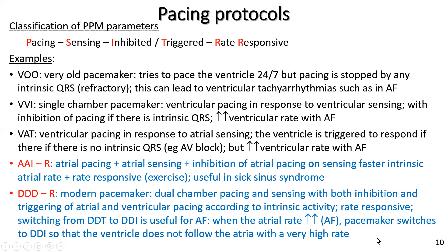It's rate responsive, so it's good in exercise. It can switch from double chamber sensing and pacing to triggering events, but can also be used to inhibit events. So it's useful in atrial fibrillation. When the atrial rate is very high, the pacemaker will switch to an inhibiting form so that it won't pace, so it will allow a lower heart rate in the ventricles so that the ventricle does not follow the atria with a very high rate. So there's a tremendous amount of clever computing and engineering in these pacemakers, and I will have more to say about them in one of the case studies in part 3 of this video series.